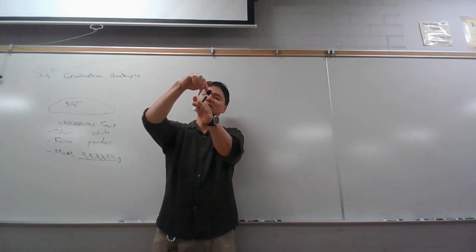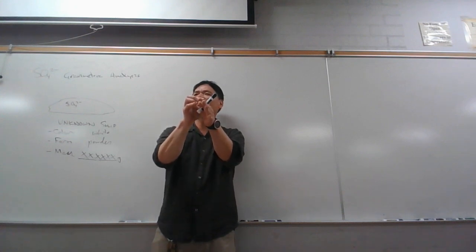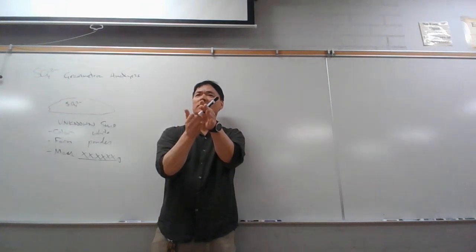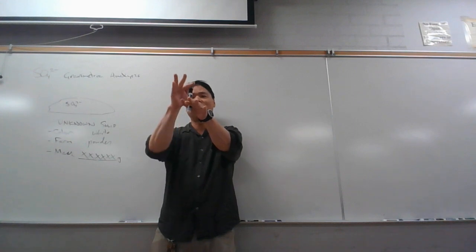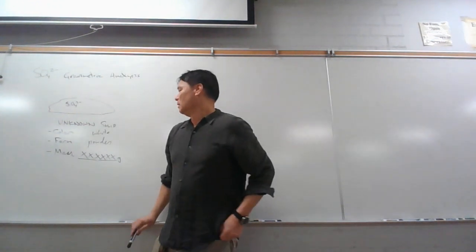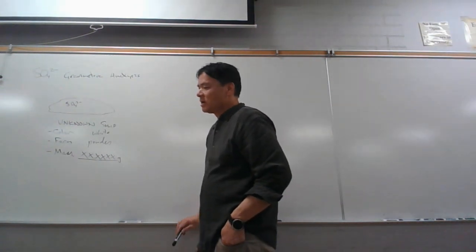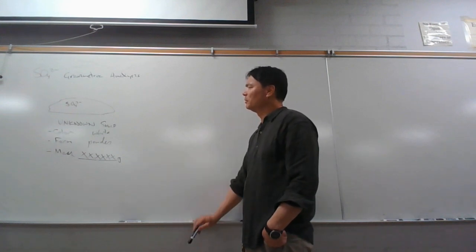If it's tilted like this, part of the mass is resting on the sleeve, and so you're going to get an inaccurate mass. And so the other thing we look for is to make sure the balance is level so that all the mass goes on the detector. Otherwise, you could be getting an inaccurate mass as well. The accuracy is very, very important.